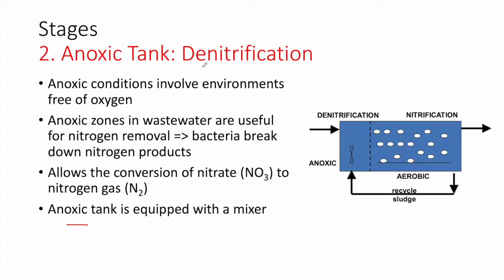Next, we have the denitrification in the anoxic tank — anoxic conditions involve environments free of oxygen, with no air diffusers. In the anoxic zones, we will be able to remove nitrogen through the proliferation of anoxic bacteria. These bacteria, starved of oxygen, will break down nitrogen products. In this stage, we have the conversion of nitrate and NO3 into nitrogen gas. Notice that the anoxic tank is equipped with a mixer.